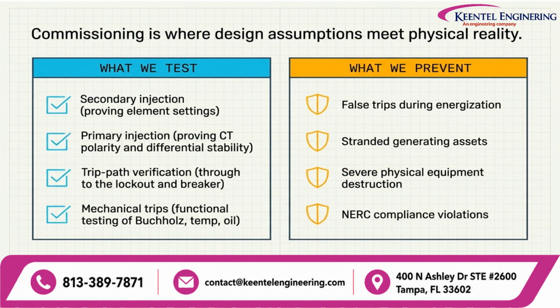The first major activity is secondary injection testing. This allows engineers to verify relay settings and confirm that the protection functions operate as expected. Primary injection testing takes the verification one step further by proving CT polarity and differential stability under realistic conditions. Trip path verification is also essential. The test must follow the actual path from the relay through the lockout relay and ultimately to the breaker.